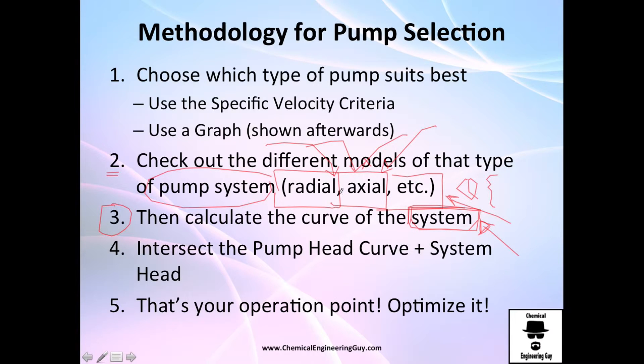Choose pumps with different diameters, compare efficiencies and requirements, then find the operation point — step four. Intersect the pump curve and the system head curve: the pump curve goes one way, the system head goes the other, and that intersection point is your operation point.